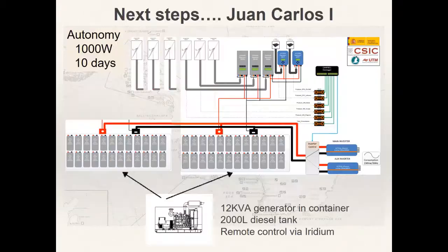In the future, in a process that will start already in the 2021 campaign, our intention is to double the power generation capacity with 3 new wind turbines and at the same time double the storage capacity. The system will be completed with a small 12 kVA diesel generator. This generator will come into operation whenever the battery banks drop below a certain level of charge, preventing the system from falling due to the lack of wind.